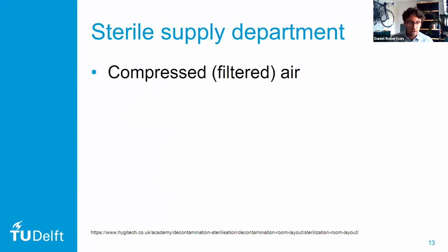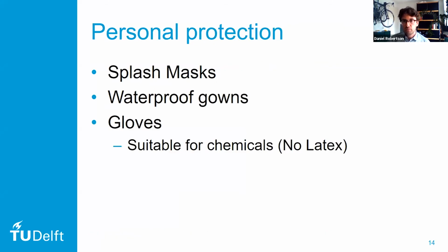Now, there are two things that are very useful in a sterile supply department in the reprocessing of laparoscopic instruments, and one of them is having compressed air, and one of them is a water jet, and I'll explain that a bit later on. Now, the other very important thing is personal protection for staff. And in all of the hospitals that we visited, the hospital didn't have any additional protection for staff besides surgical masks and latex. While scrubbing the instruments, you generally use a brush, and the debris can splash, and even microbes can become aerosolized. So proper splash masks for staff are really important. And this is the same for waterproof gowns. And the other one is having suitable gloves for reprocessing. So some of the disinfectants and detergents, like enzymatic cleaners, will actually start to dissolve the latex gloves. And also when handling sharp instruments, it's recommended to have a thick pair of gloves.